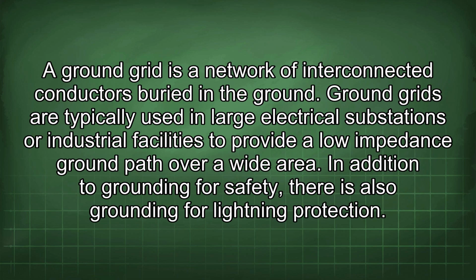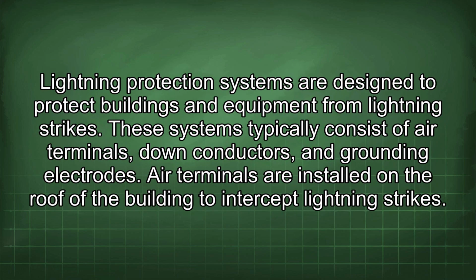A ground grid is a network of interconnected conductors buried in the ground. Ground grids are typically used in large electrical substations or industrial facilities to provide a low-impedance ground path over a wide area. In addition to grounding for safety, there is also grounding for lightning protection. Lightning protection systems are designed to protect buildings and equipment from lightning strikes. These systems typically consist of air terminals, down conductors, and grounding electrodes.